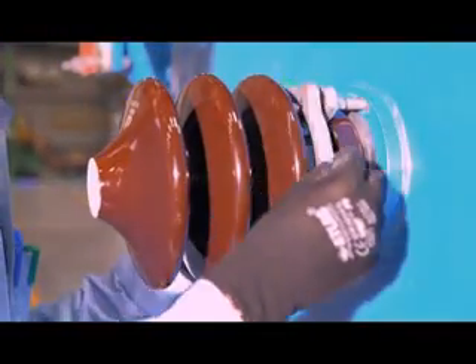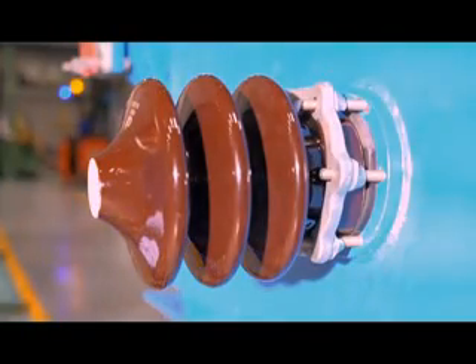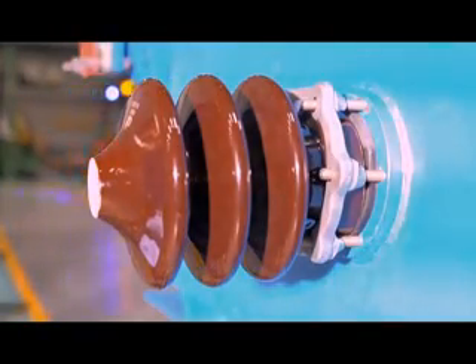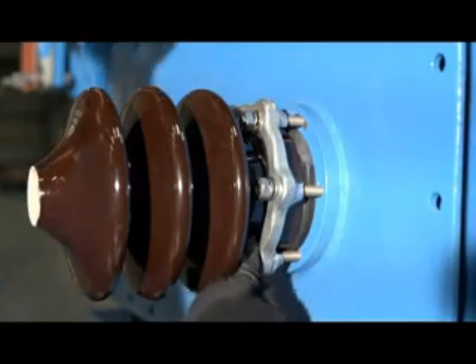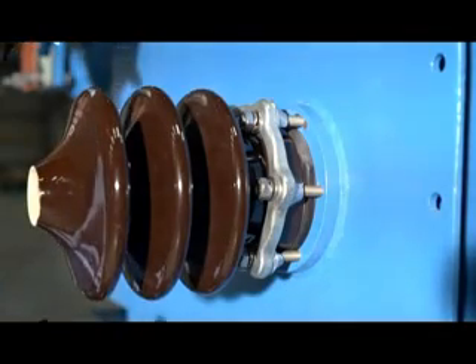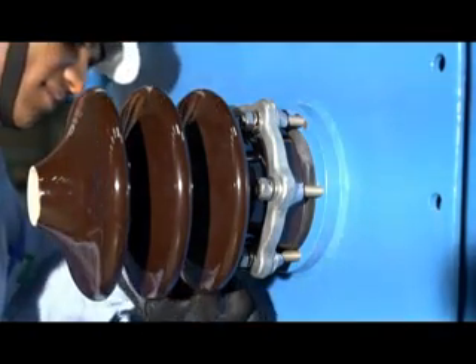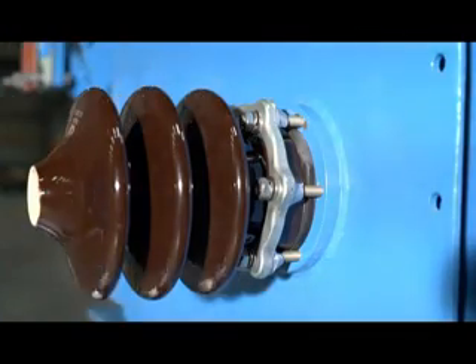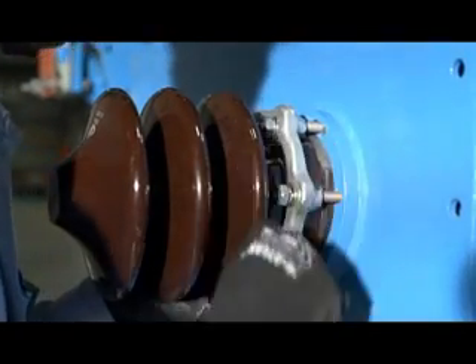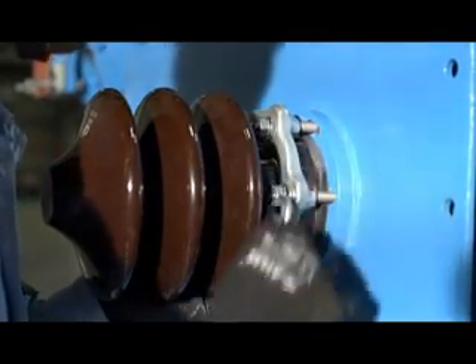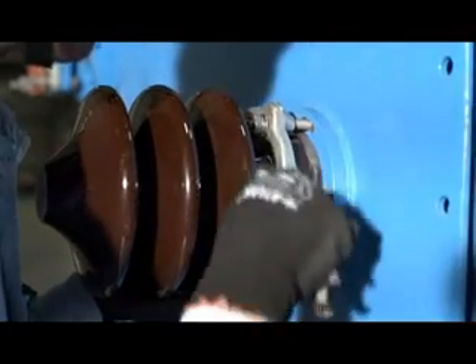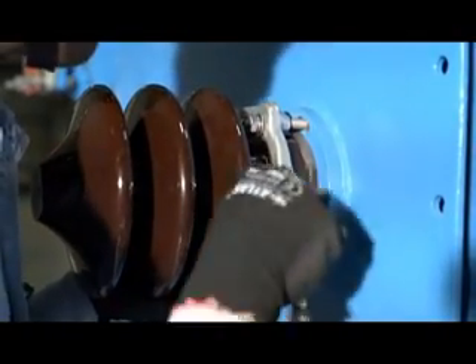High current low voltage connections for core coil assemblies are made with copper bus bars, which are connected to the bushing by means of flexible risers. The terminations can be either on the cover plate or on the side of the tank. These can be housed in special cable boxes as per requirement.